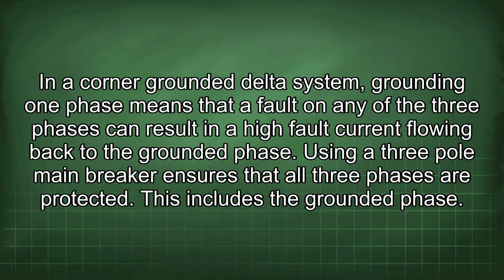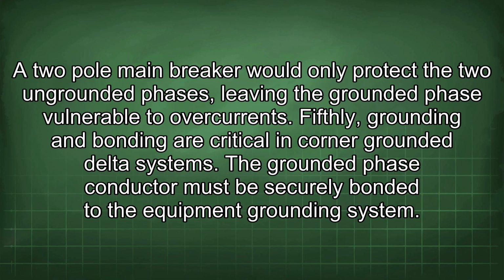Using a 3-pole main breaker ensures that all three phases are protected. This includes the grounded phase. A 2-pole main breaker would only protect the two ungrounded phases, leaving the grounded phase vulnerable to overcurrents.